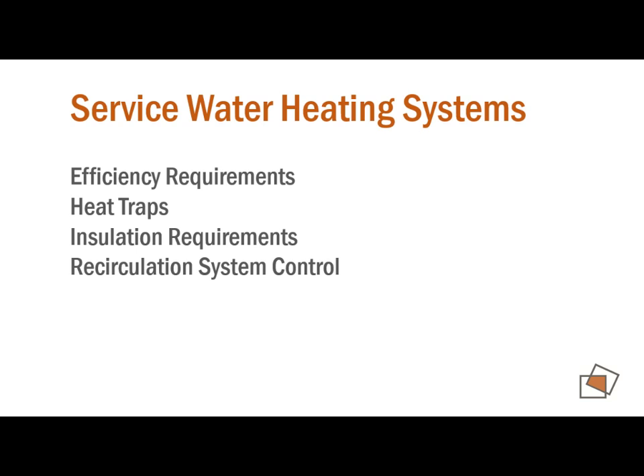You need to be able to shut it off based on loop temperature or time, a timer or something to say the building's not occupied. In the 2018, it goes a little bit farther with what's required there, saying that you can't even run the pump. It needs an occupancy, a flow detection or some sort of occupancy detection, or else the pump can't even run.